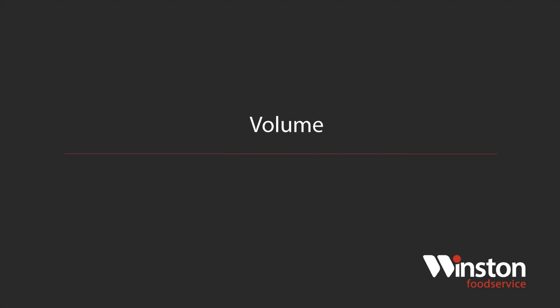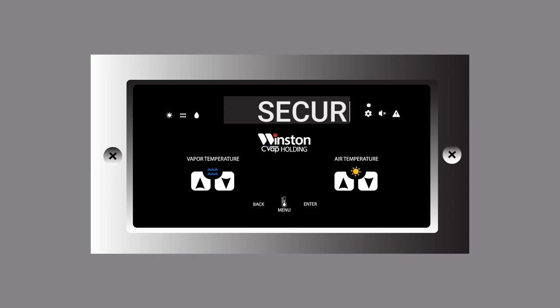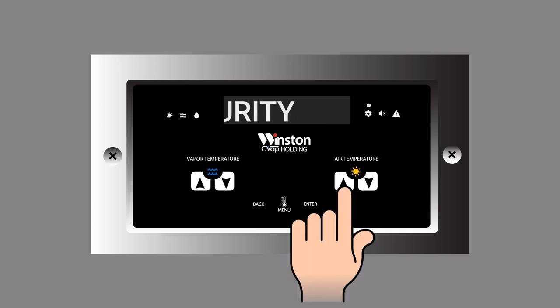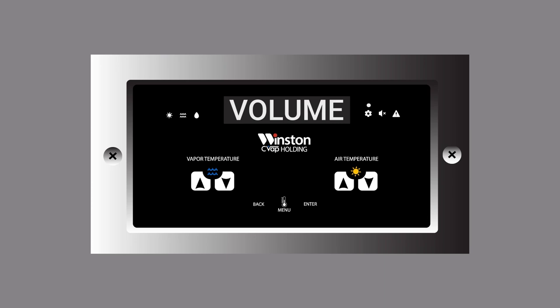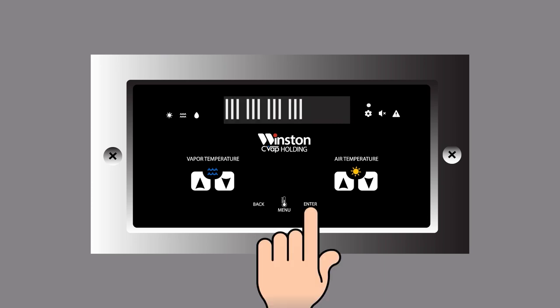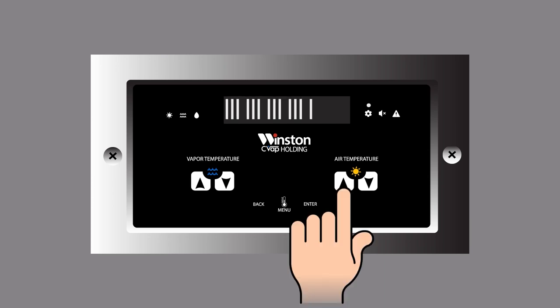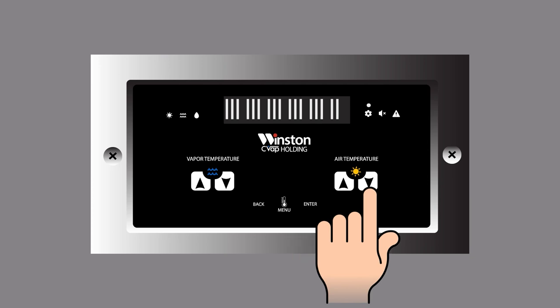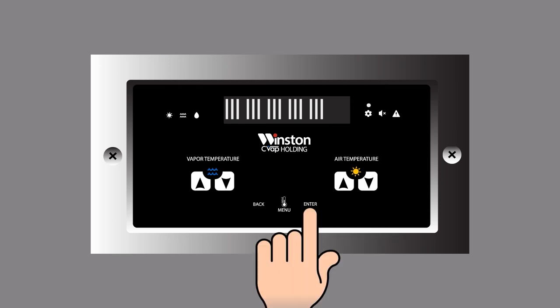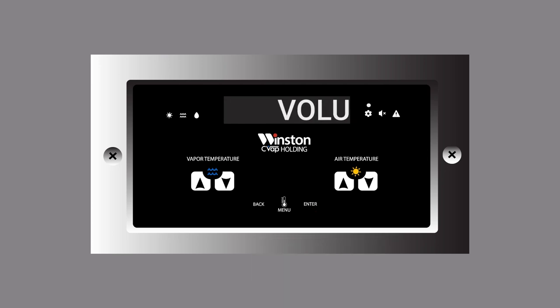Volume. This allows the user to change the volume settings for the unit. With security displayed, press the air temperature up button and volume will be displayed. Select Enter. Bars will appear that indicate controller volume. Using the air temperature up and down buttons, the controller volume can be raised or lowered. Set the desired volume and press Enter. Volume will be displayed.